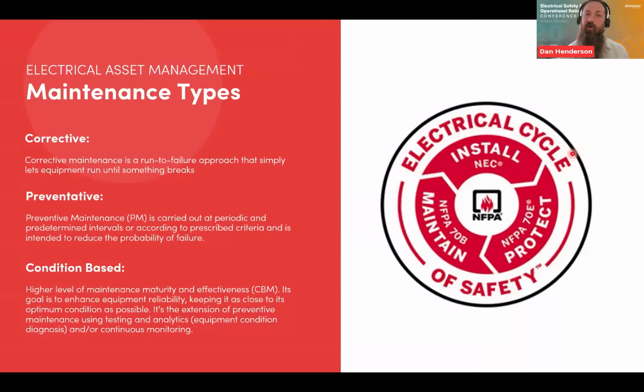It's not a finger-pointing exercise, but it is difficult to always be where you need to be and up to date. And obviously, following on the cycle of safety from within NFPA 70, by following that process, install it in the right way with the right codes, the right standards, following 70E to make sure you've got that protection of people, and you maintain it in line with 70B. In reality, we should be reducing the likelihood of having an incident.